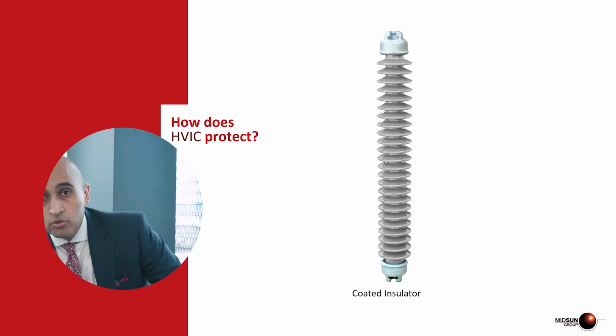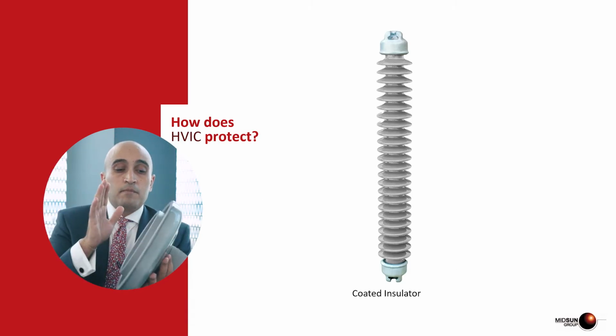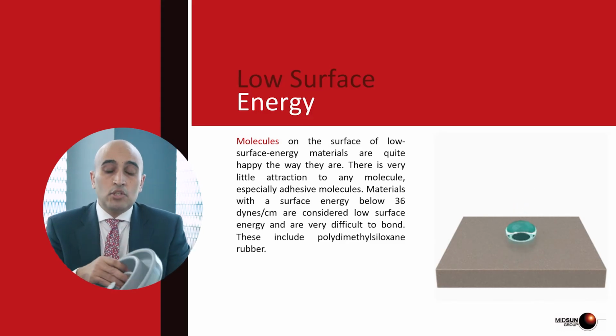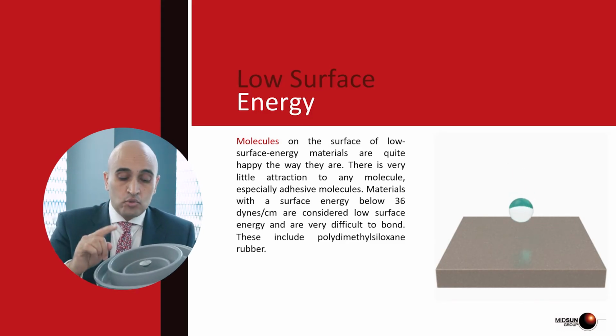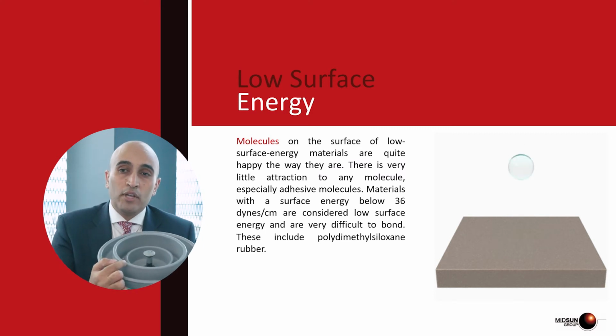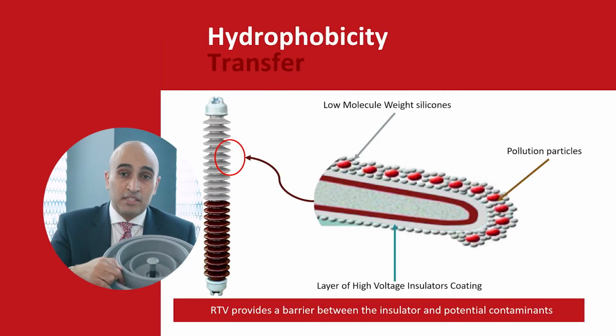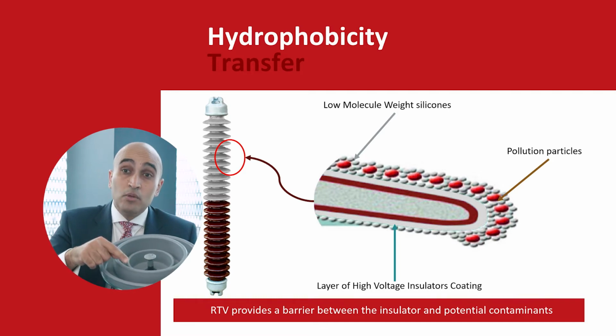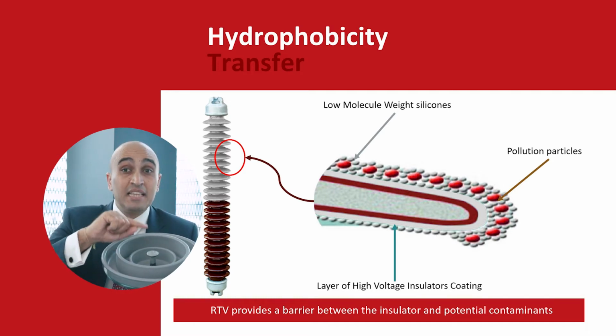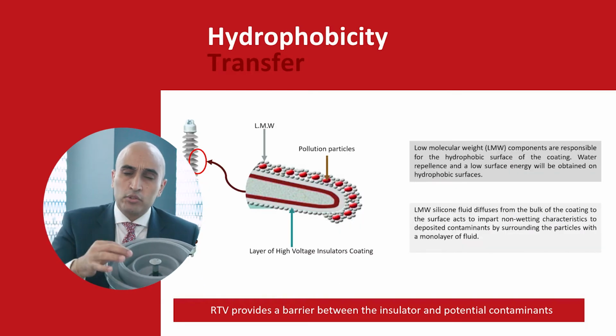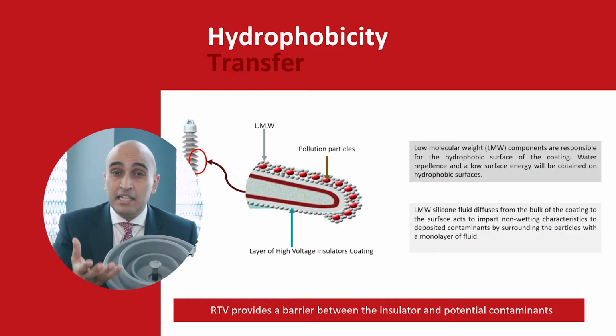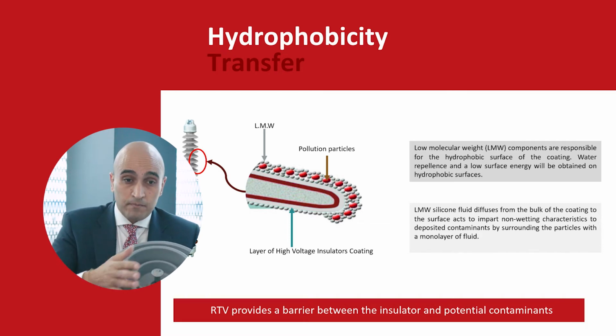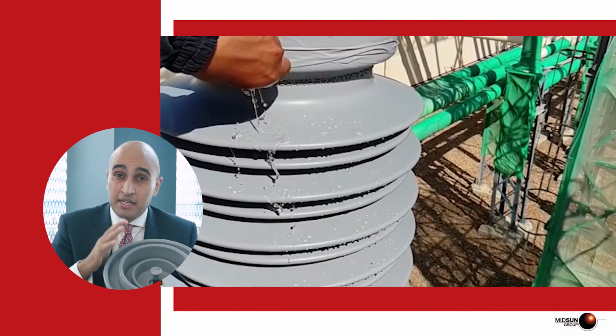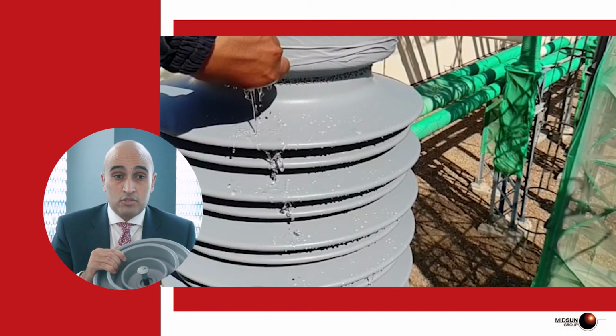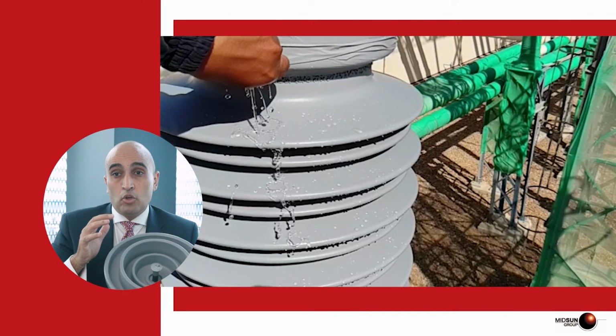However, a coated insulator has low surface energy, and this low surface energy, added to the liberation of low molecular weights that are in the bulk of the RTV coating, which in turn will coat the contaminants and render them hydrophobic, will prevent water from filming, so we will not have any leakage currents, ergo we will have no flashover. This is one of the main characteristics of RTV coating on high voltage insulators: the hydrophobicity and the low molecular weights that encapsulate the contaminants.